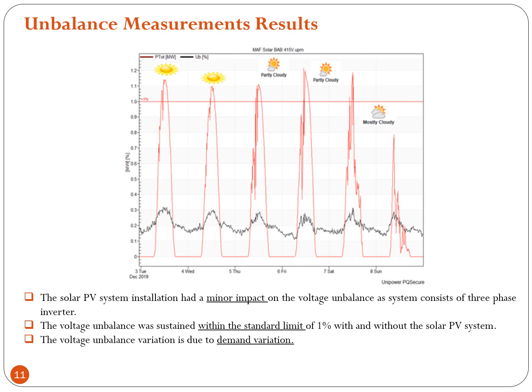The result of the unbalance measurement shows that the solar PV system installation had a minor impact on the voltage unbalance, as the system consists of a three-phase inverter. The voltage unbalance was sustained within the standard limit of 1% with and without the solar PV system. The voltage unbalance variation is due to the demand variation.